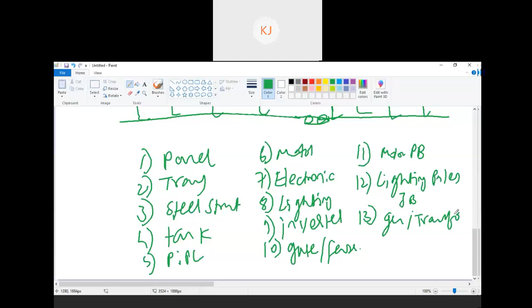Even PV array, right? The whole photovoltaic array is also grounded. But the reason I didn't mention that is photovoltaic is a different subject - building and industrial earthing will not cover that because it is totally different. Actually, I did research on that for 8-9 months and made a small training module on it also, and it is a completely different subject, because there the fault current will not increase in a PV array.